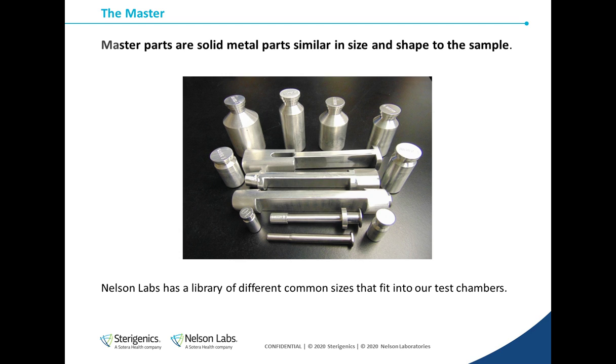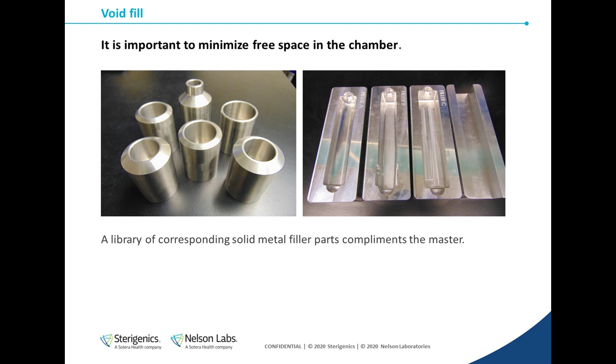We use the master to verify that the test system is clean, dry, and free of virtual leaks or residual mass. If the master doesn't pass the test, then that indicates that there's something wrong with the test system that needs to be removed or corrected before the samples can be accurately tested.